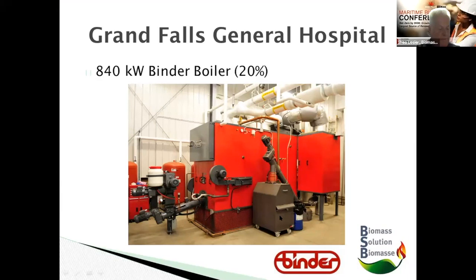It's important to notice that calculating the proper boiler and buffer tank size on any biomass heating system is very important. This combination will play a major role in the efficiency results at the end. As an example, the boiler here is oversized, but we are efficient because of the huge size of the buffer tank, and also because this boiler's full capacity can modulate down to 20%, which makes for longer heating cycles and helps in the summertime to provide heat to the domestic water.